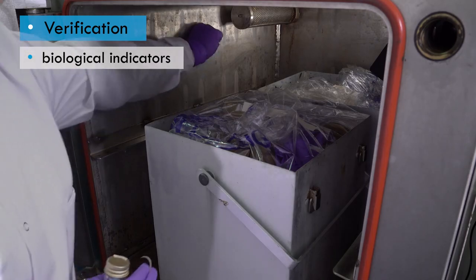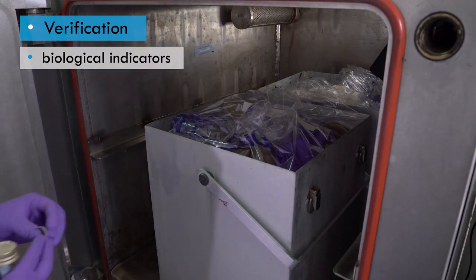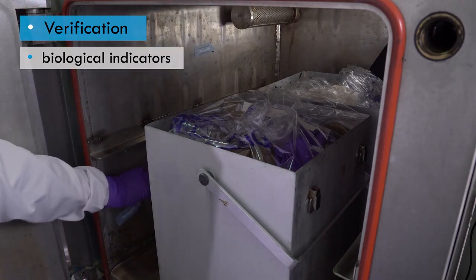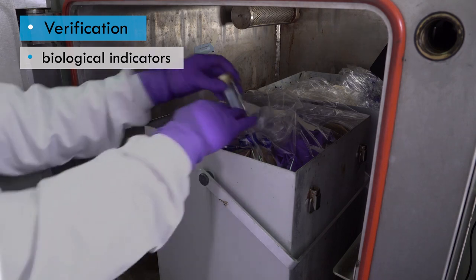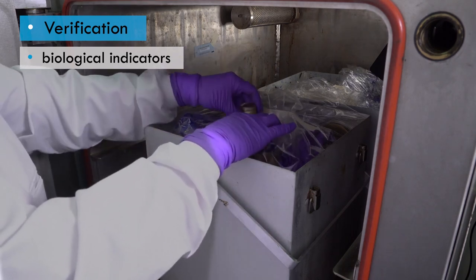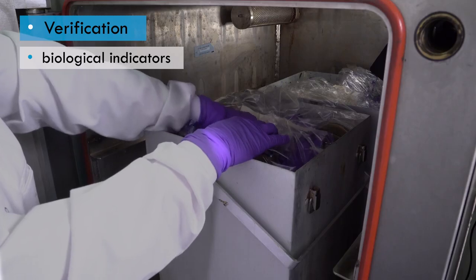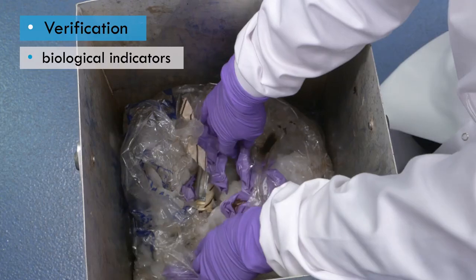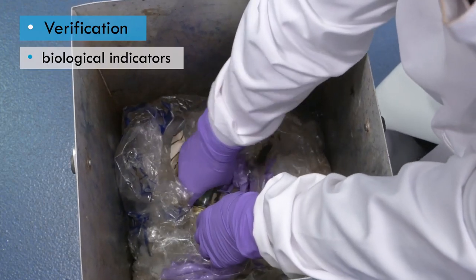Spore strips or discs are generally placed at various locations within the autoclave to ensure that all areas reach the required parameters. They can also be placed within a typical autoclave load, although it can prove difficult to extract them from the load when the autoclave cycle is complete.